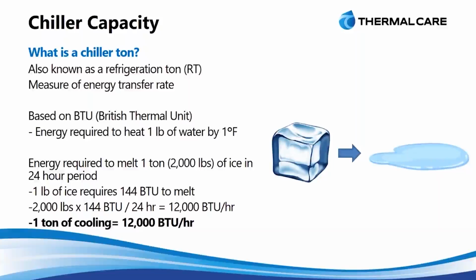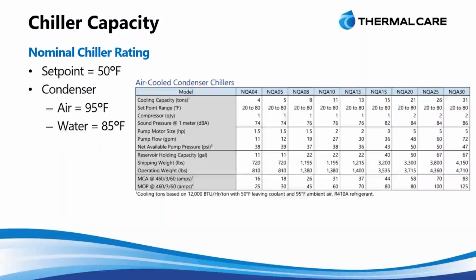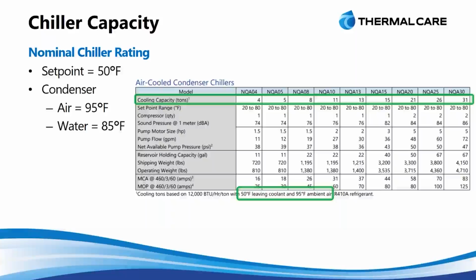And the reason that I talk about that is because we're going to start talking about the ratings of chillers, because that's really the major selection point of a unit: does it have the capacity to provide enough cooling for your process? So what I have here is a typical spec sheet chart from a Thermal Care spec sheet for our NQ series chillers. In this, we can see the cooling capacity is denoted in tons. If you see that superscript there, that'll lead you down to a footnote. And what it points out is there are some conditions that we are using to rate these chillers. And we call that a nominal chiller rating. It's based upon a 50-degree leaving water temperature and a 95-degree ambient air, or in the case of a water-cooled unit, it would be 85-degree water.